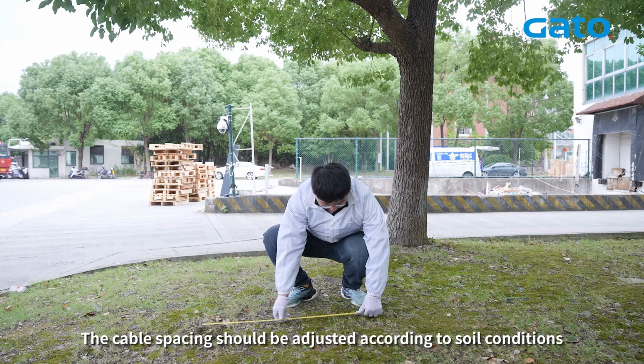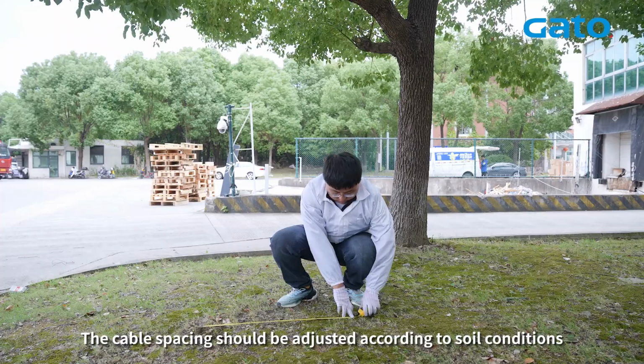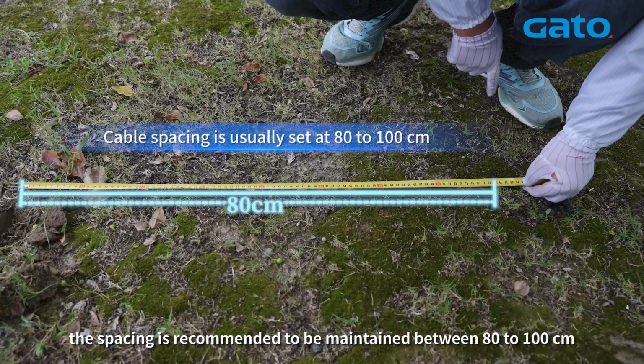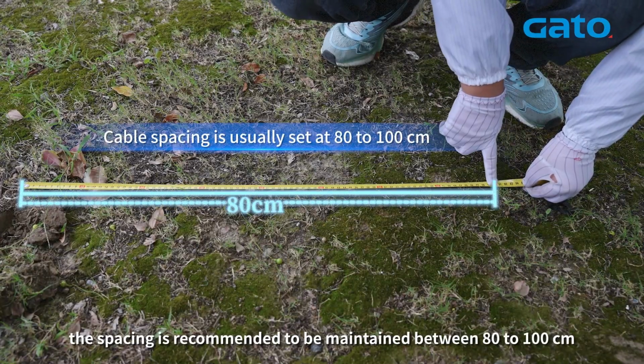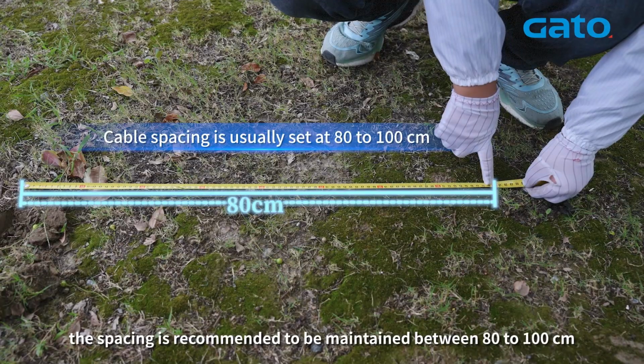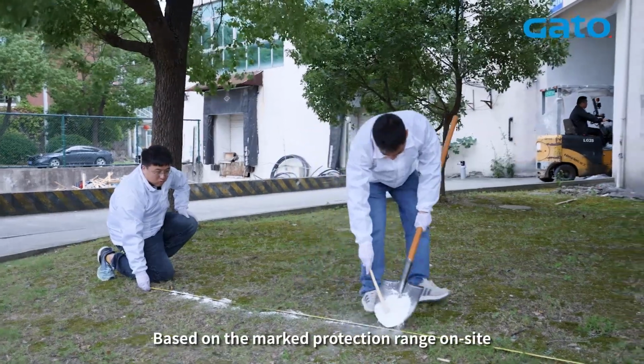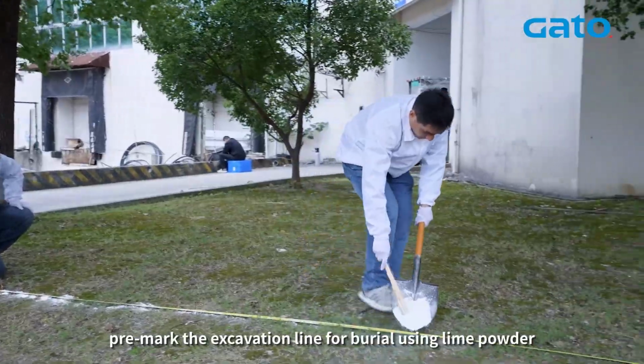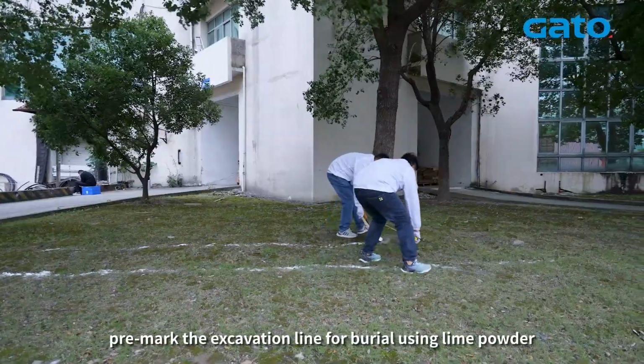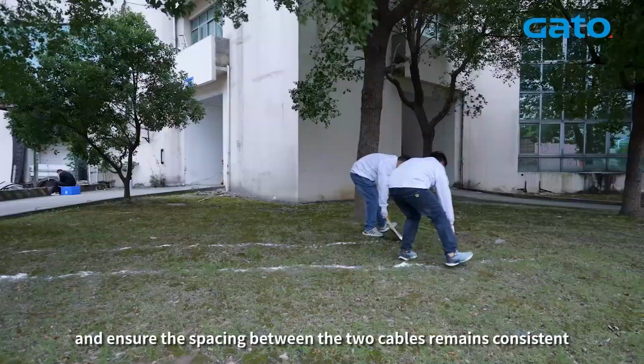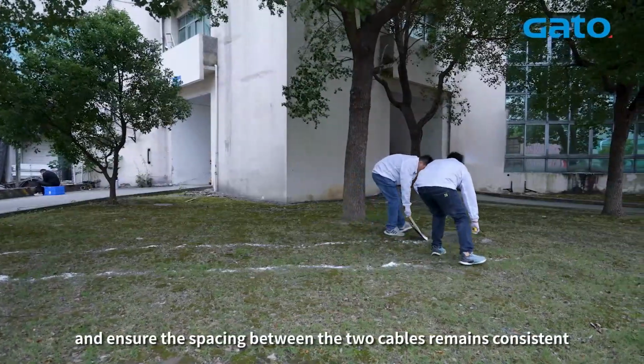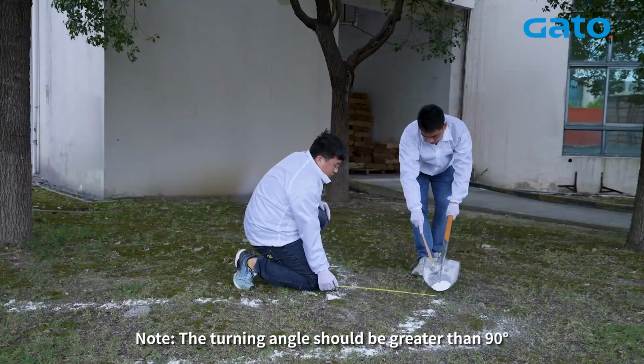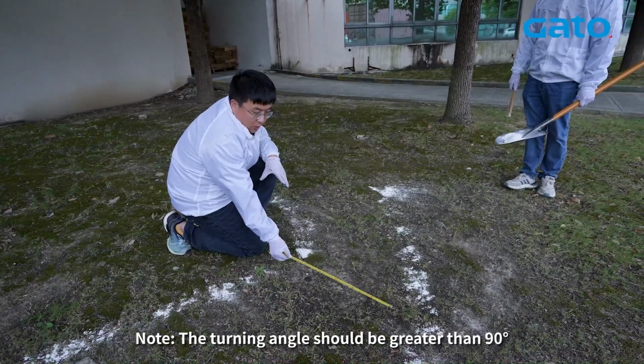The cable spacing should be adjusted according to soil conditions. In ordinary soil, the spacing is recommended to be maintained between 80 to 100 centimeters, based on the marked protection range on site. Pre-mark the excavation line for burial using lime powder, and ensure the spacing between the 2 cables remains consistent. Note: the turning angle should be greater than 90 degrees.